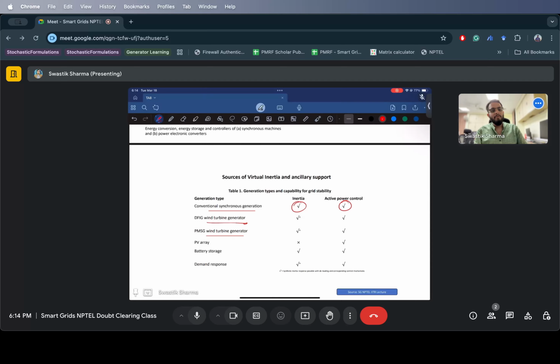But still, by controlling the headroom, by controlling the amount of power it is converting or giving back to the grid, you can have some form of synthetic inertia from the system. And by controlling set points, you all know you can control active power. For PV array, there is no such arrangement.